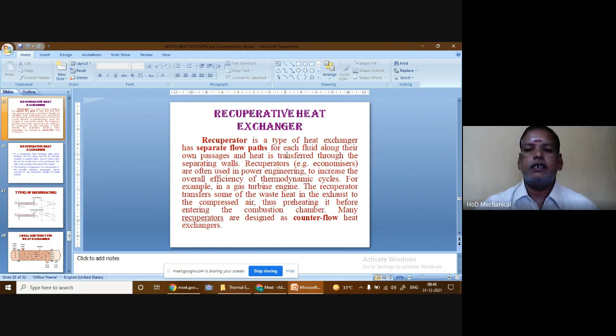In a recuperator, the heat exchange takes place between the flue gases and the air through the metallic or ceramic walls. Ducts or tubes carry the air for combustion to be preheated. The other side contains the waste heat stream. The simplest configuration for a recuperator is the metallic radiation recuperator, which consists of two concentric lengths of metal tubing.